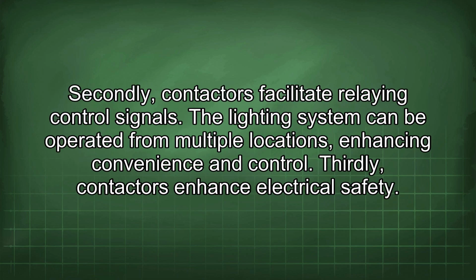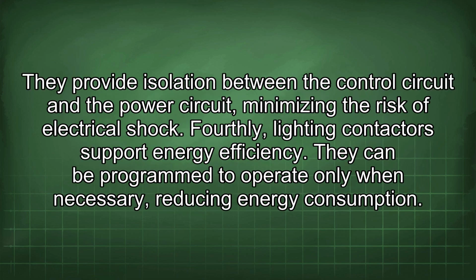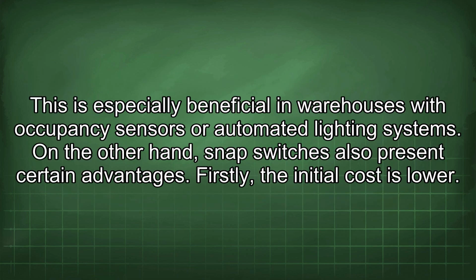Secondly, contactors facilitate relaying control signals. The lighting system can be operated from multiple locations, enhancing convenience and control. Thirdly, contactors enhance electrical safety. They provide isolation between the control circuit and the power circuit, minimizing the risk of electrical shock. Fourthly, lighting contactors support energy efficiency. They can be programmed to operate only when necessary, reducing energy consumption. This is especially beneficial in warehouses with occupancy sensors or automated lighting systems.